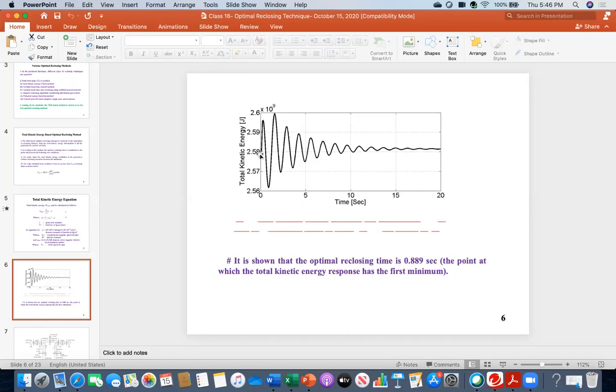Once there is a fault, we are assuming the fault here at 0.1 second, and you see the total kinetic energy went up. Total kinetic energy is very similar to speed change. You have noticed that in the case of a synchronous generator or even an induction generator, following a fault, speed goes high. Total kinetic energy is calculated with the help of speed, like half m v squared, half J omega squared. That's why the total kinetic energy response is also very similar to speed. You see, the fault happens, it goes up and then comes down, and after some oscillation, around 15 seconds, it settles down. It became the original value, 2.58 times 10 to the power 9 joule, at this level.